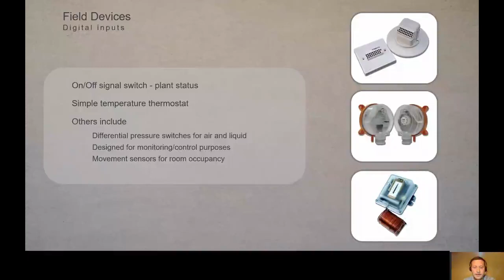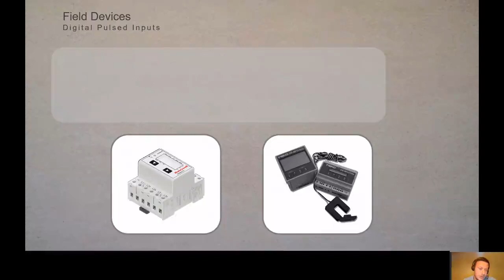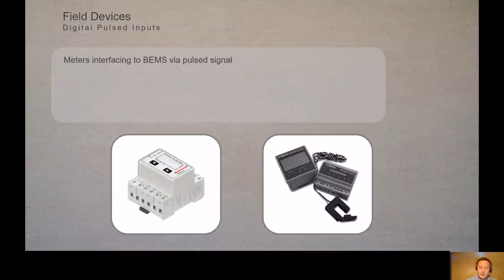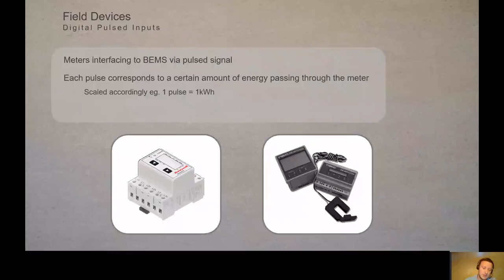So these are just single point values that you're looking for to be brought back into the controller. You can also have a third one, which is still effectively a digital, but it's just reading it quite quickly, and this is from a digital pulse perspective. So you'll have a scaled value whereby you'll read a pulse, and that pulse can equate to a specific number. So it could be a kilowatt, it could be 10 kilowatts, could be 100 kilowatts, whatever the scaling is. But that will normally be read from the manufacturer, where we're just counting pulses and then putting that value into the controller.